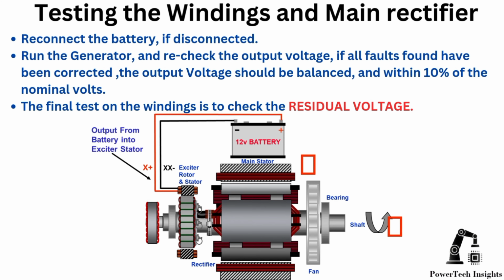Testing the windings and main rectifier. Reconnect the battery if disconnected. Run the generator and recheck the output voltage. If all faults found have been corrected, the output voltage should be balanced and within 10% of the nominal volts. The final test on the windings is to check the residual voltage.